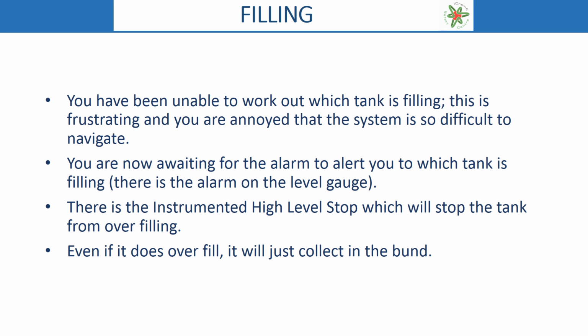This is frustrating and you're annoyed at the system. It's so difficult to navigate. You now have to wait for the alarm to alert you which tank is filling. There is an alarm on the high level gauge at least. There's also the instrumented high level stop, which will stop the tank from overfilling. Even if it does overfill, it'll collect in the bund. These systems give you confidence that nothing can happen.